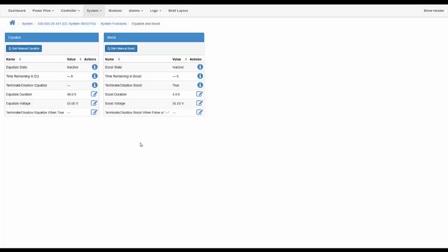As we are here on the new Equalize and Boost page, there was a termination condition added to the Equalize and Elevated Absorption modes as well. The termination field for Equalize is here, as you can see. Terminate, disallow Equalize when true, and then you can select what it is that you would like to monitor as being a true or false condition.